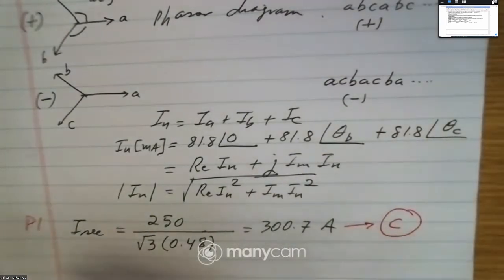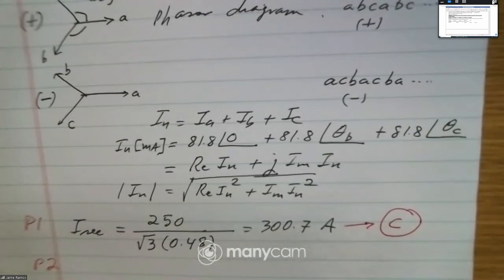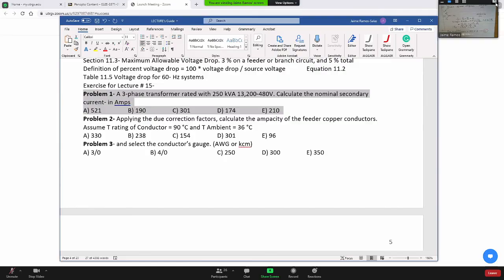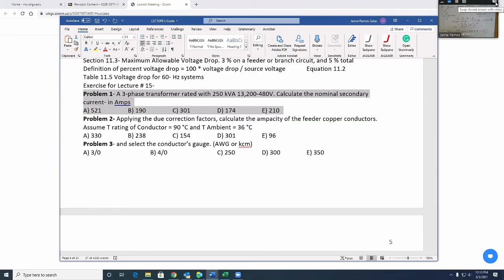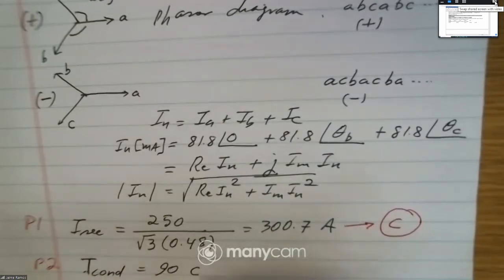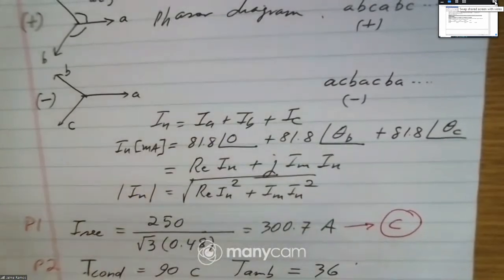So that's problem 1. Now problem 2, it says correction factors. Calculate the ampacity of the feeder copper conductor. Assume T rating of the conductor. So T conductor, 90 degrees. T ambient, 36 degrees. So correction factor for 36 degrees. So that's going to be 0.91.